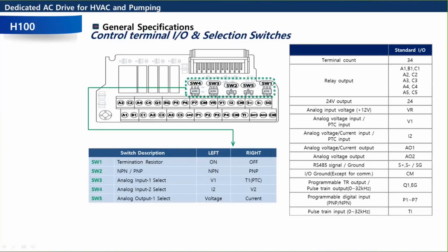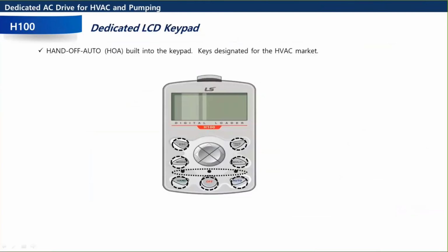You could switch between 4 to 20 milliamps and 0 to 10 volts DC. And then we have our analog output that we could switch from voltage to current. So there's some flexibility in here. It's pretty much just changing a dip switch, so no parameters associated with them, besides the functionality, that's a parameter.